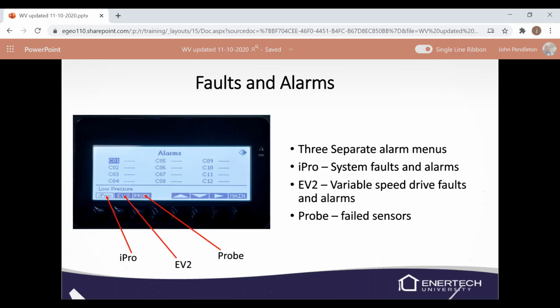If you press the alarms button in the lower right corner, it'll take you to the alarms menu. Now, when you get to the alarm menu, you can see the little red lines there. There are 3 different alarm menus: the iPro, which is the one you're in now, the EV2, and the probe. iPro is where you're normally going to find most of these. It's going to be your system faults and alarms. Your EV2 are your variable speed drive faults and alarms, and the probe are your failed sensors. We don't have sensors fail very regularly. Normally, you're going to fault out on flow or high pressure, low pressure, something like that. So it'll normally be on your iPro screen.